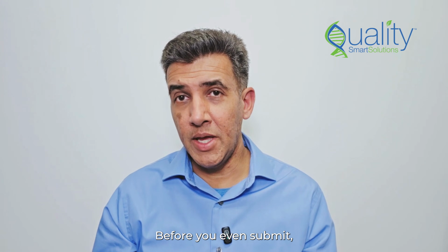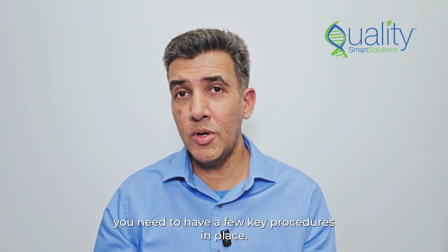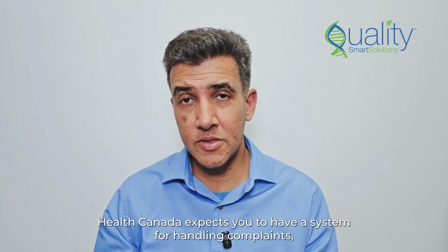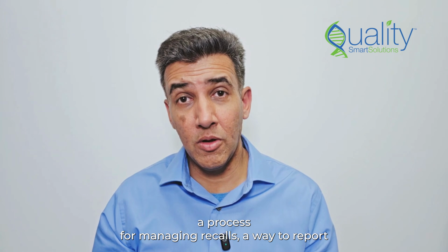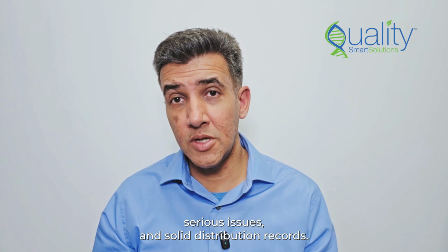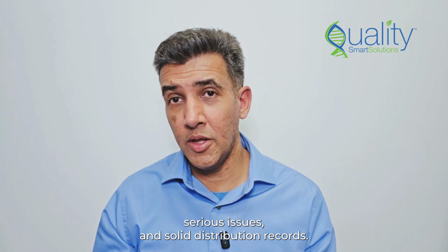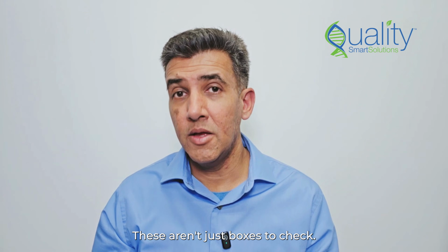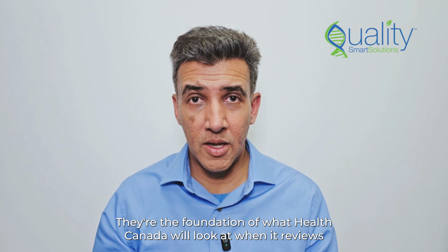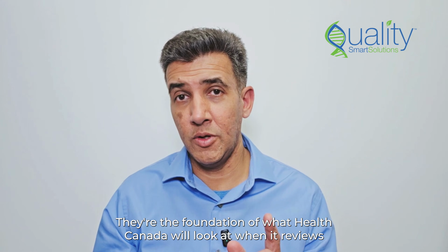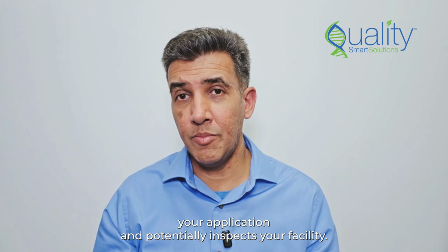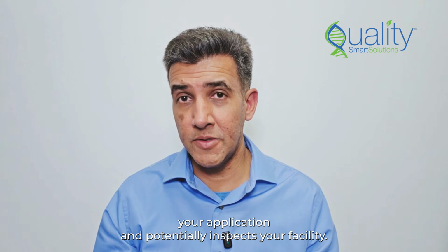Before you even submit, you need to have a few key procedures in place. Health Canada expects you to have a system for handling complaints, a process for managing recalls, a way to report serious issues, and solid distribution records. These aren't just boxes to check, they're the foundation of what Health Canada will look at when it reviews your application and potentially inspects your facility.